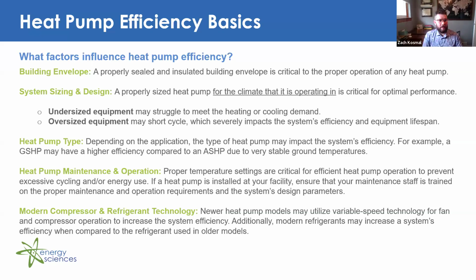In addition, system sizing and design is also very important. A properly sized heat pump for the climate that it is operating in is critical for optimal performance. An undersized piece of equipment may struggle to meet that heating or cooling demand, whereas oversized equipment, as we just mentioned, may short cycle. Short cycling severely impacts that system's efficiency and equipment lifespan. You also have heat pump equipment types. Depending on the application, the type of heat pump may impact a system's efficiency. For example, a ground source heat pump will likely have a higher efficiency compared to an air source heat pump due to very stable ground temperatures versus very unstable outside air temperatures.